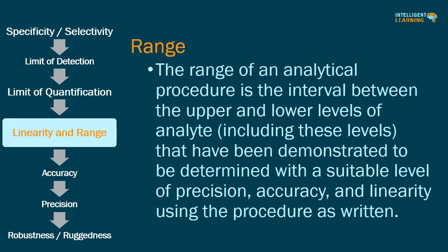The range of an analytical procedure is the interval between the upper and lower levels of analyte — including those levels — that have been demonstrated to be determined with a suitable level of precision, accuracy, and linearity using the procedure as written. The lower end of the range is bounded by the LOQ, and the upper end is defined by concentrations at which significant anomalies in analytical sensitivity are observed. Various documents use the term range or working range.